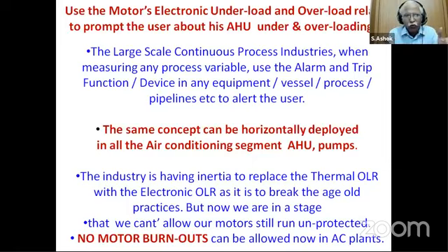It is a foolproof mechanism, even at any point of loading, say at 50% loading of a given AHU. The thermal overload relay will definitely not sense and work in case of any unbalance or single phasing. But in the case of an electronic motor protection relay, definitely the AHU is saved. And it also indicates to the user that the blower or the AHU is running at only 50%. You have to take action.